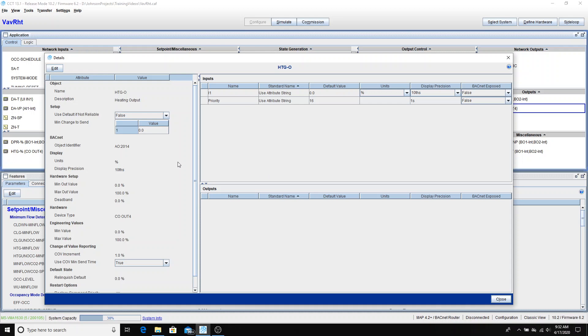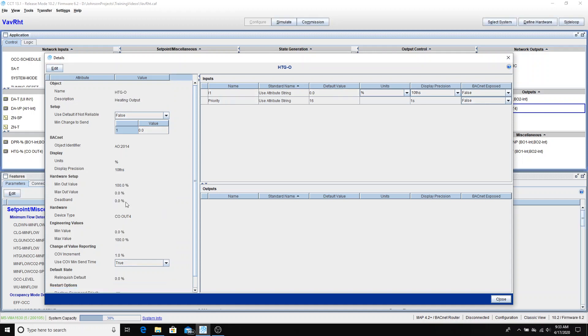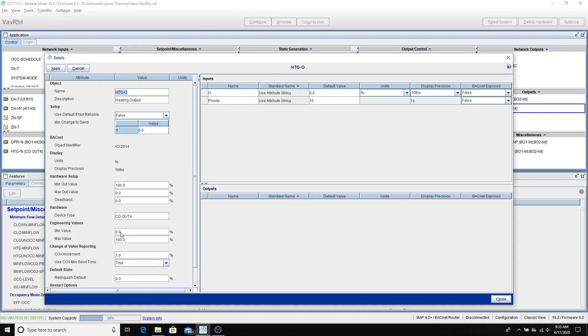And then by the same token on the heating output, if we have a normally closed valve, 0 to 10 volts opens the valve, then we can set, under our hardware settings, we can leave this setting 0 to 100%. If it was a reverse acting valve, normally open, where 10 volts is closing the valve, then we would swap these two values. I would put 100 in our min value and 0 in the max value. And we can apply that. You can see it will take it. If we add a 2 to 10 volt actuator as opposed to a 0 to 10, we could go into Edit, make the min output value 20%. That would give us 2 to 10. So that's how you would adjust for either 2 to 10 or reverse acting or direct acting.